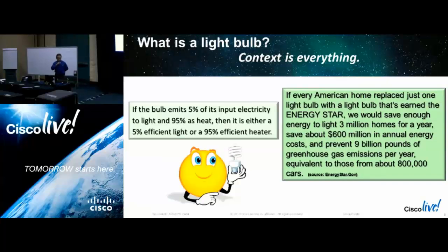But what's our context? What's your context when you talk about energy management? Is it power or is it energy? Power, measured in kilowatts, comes through that big pipe outside the building, through the utility meter, and it ultimately ends up at the IT load. And that pipe has to be big enough to handle all those kilowatts that IT load is ever going to need at any one time. That is a CapEx problem, a CapEx question.